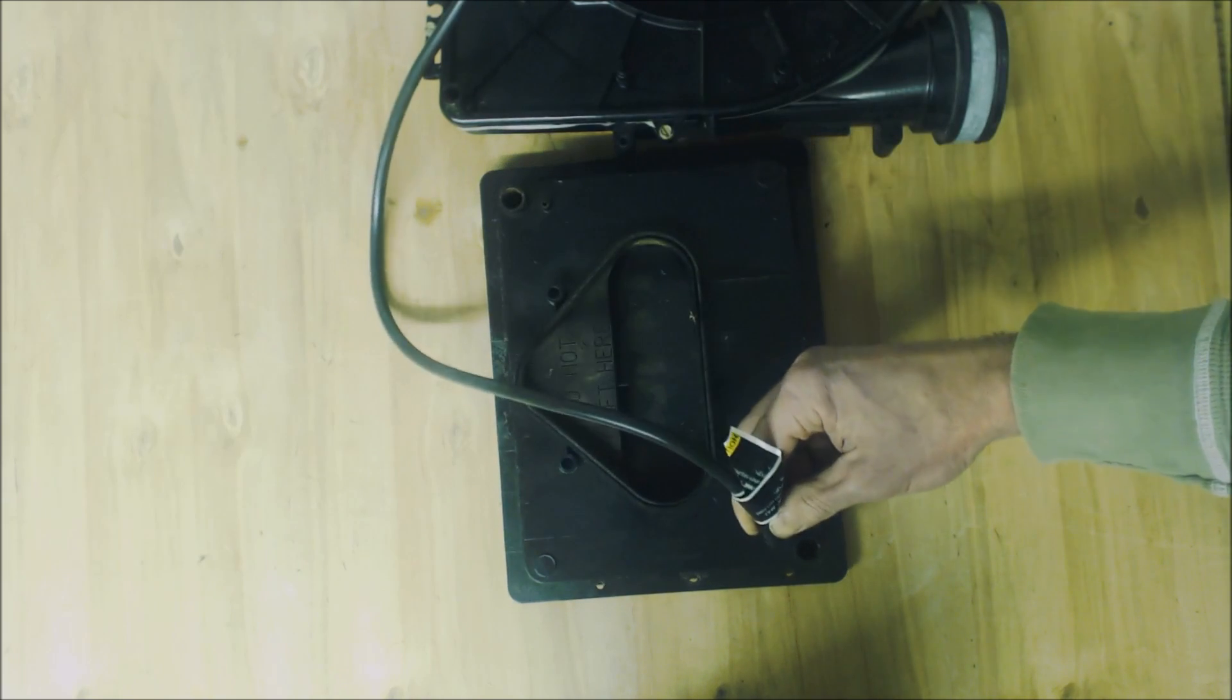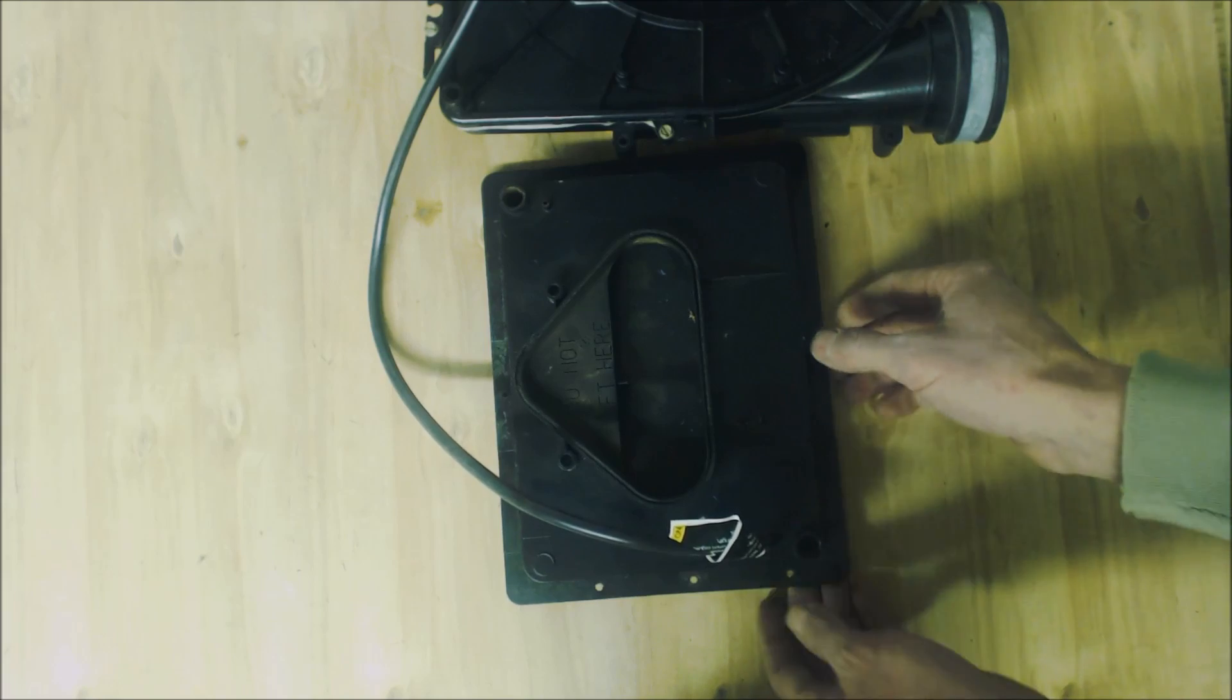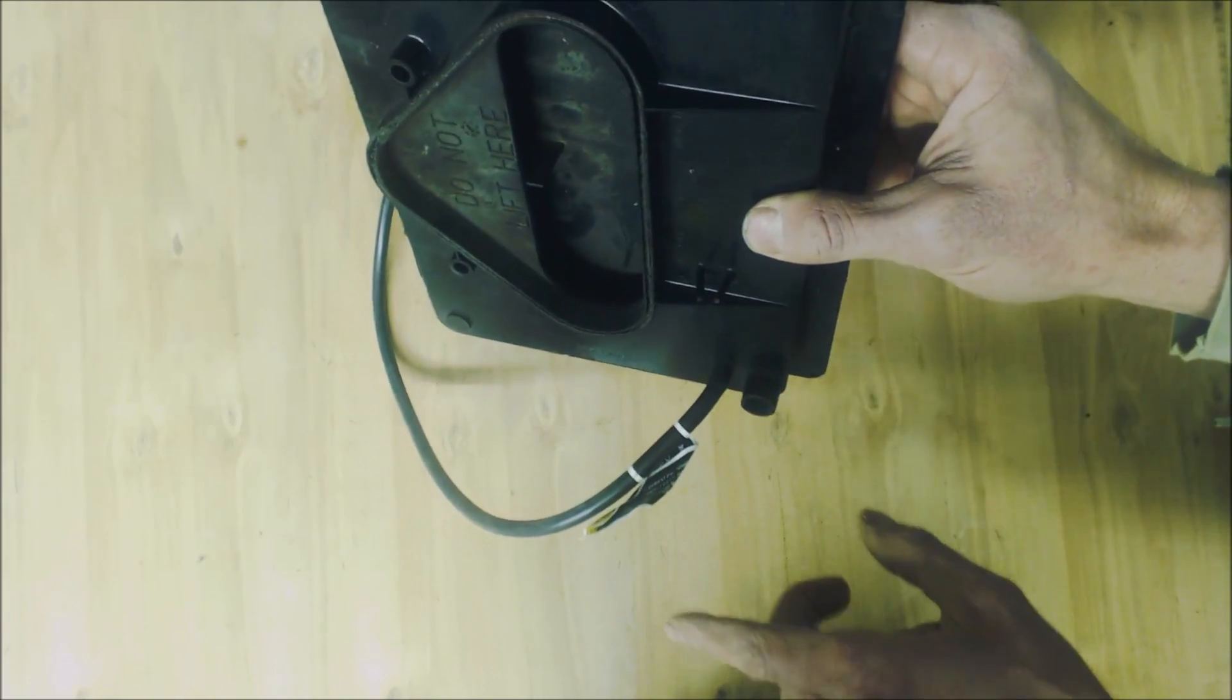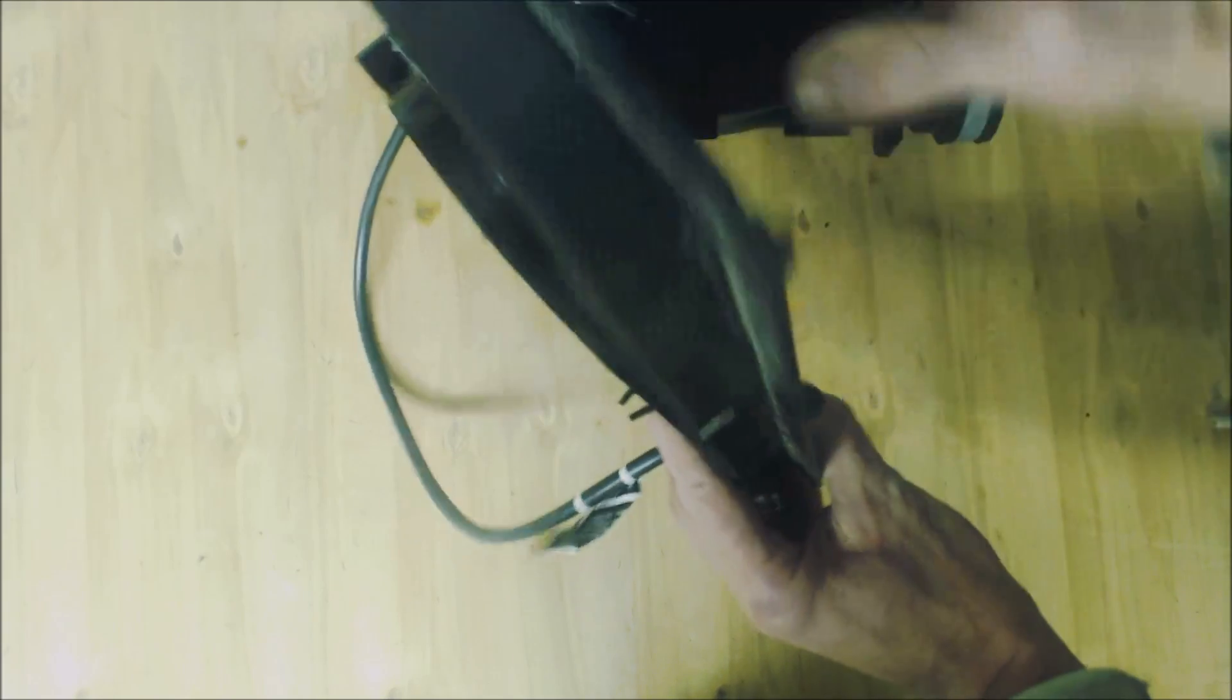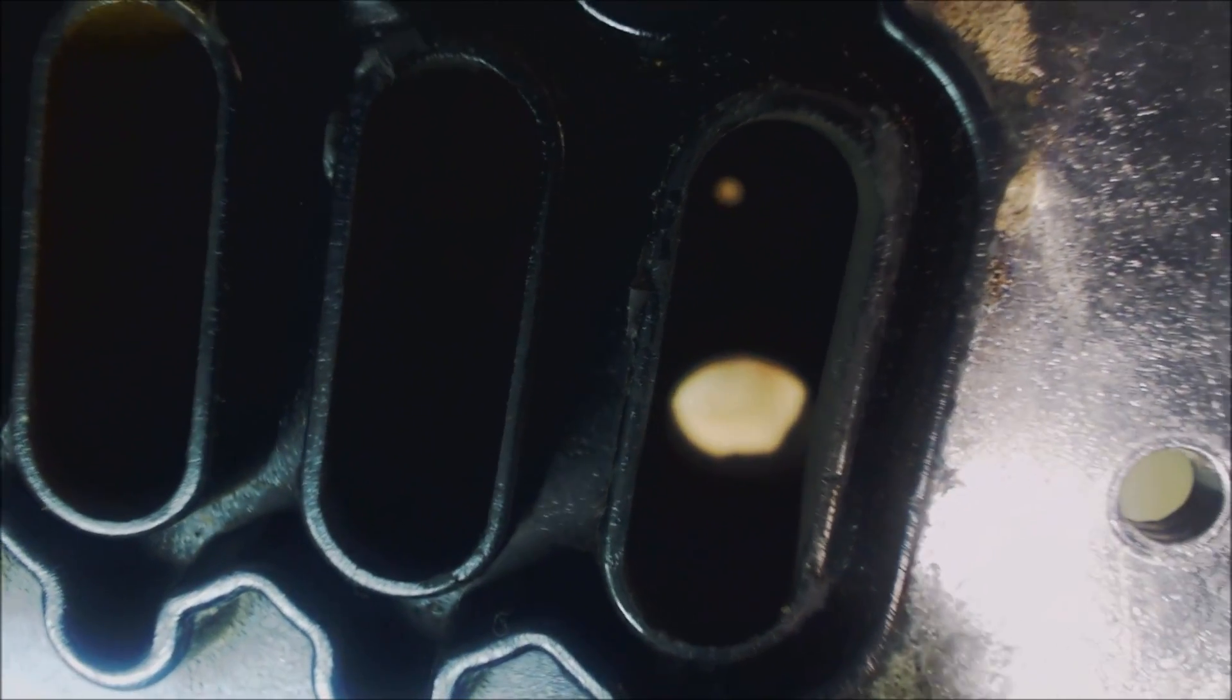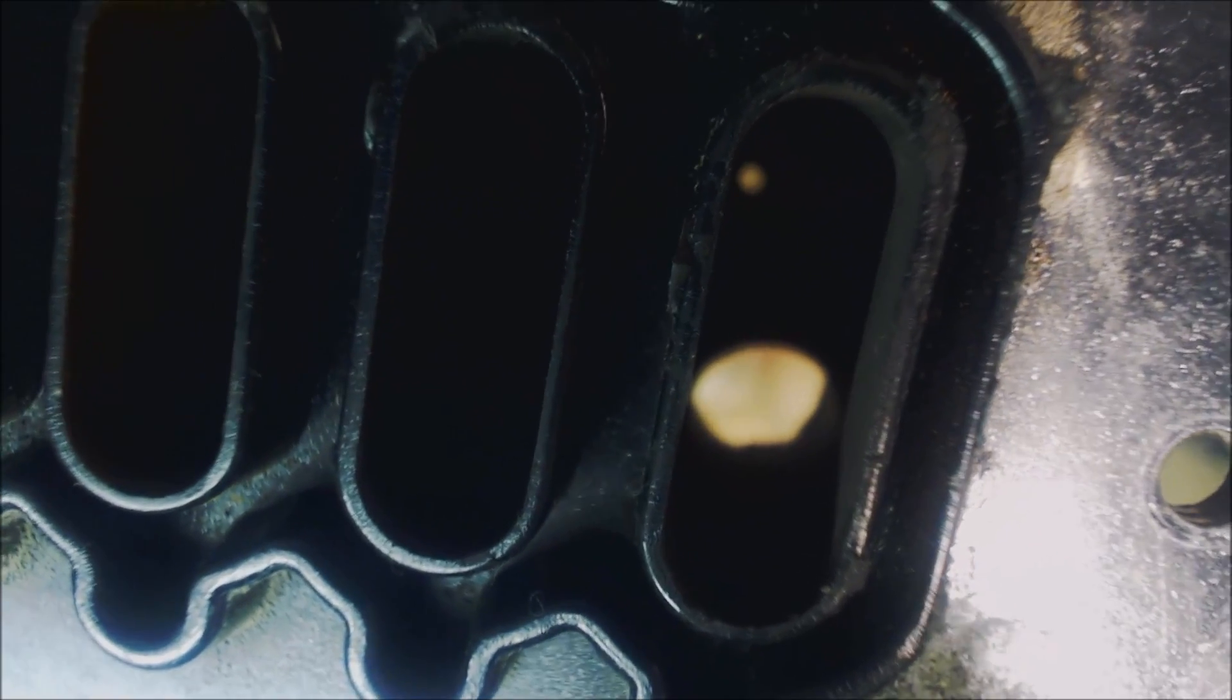The reason that they're checking for the condensate buildup is this is the main drain right here and this drains out. This goes to a condensate trap. If you look back here, you see the smaller hole above the large hole. That is the condensate tube that goes to the pressure switch.